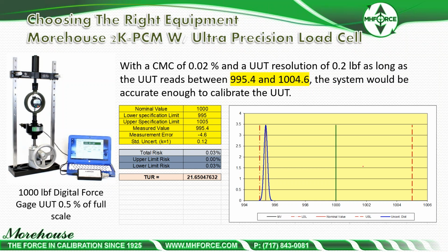But in this, we have to subtract the uncertainty of the reference, and we have to look at the resolution and repeatability. So in this case scenario, we have a TUR of 21.65 using our PCM, and we still can't make that statement of compliance unless the measurement falls within this. And that's really what we're saying. So I'll have less than 2% risk if my measurement is above 995.4 and under 1004.6.